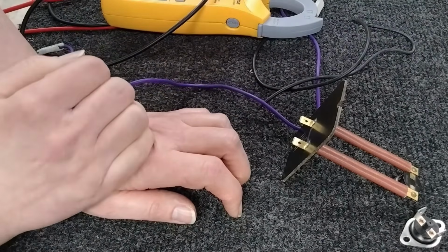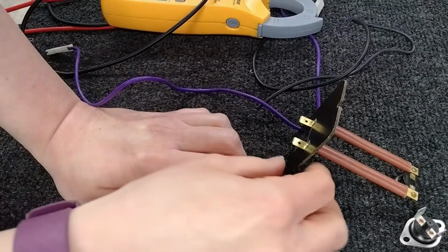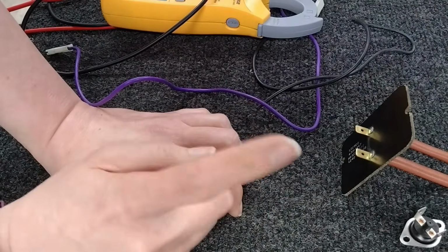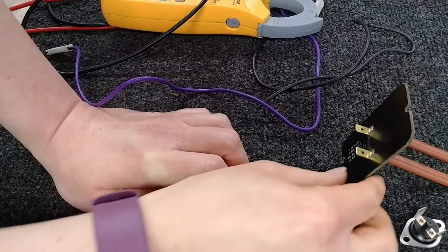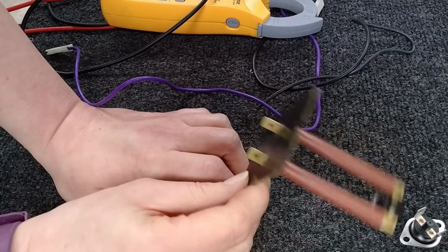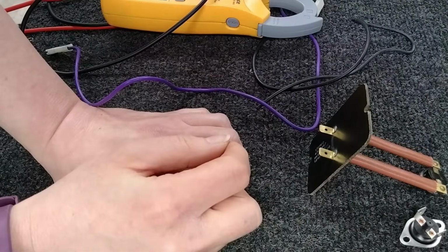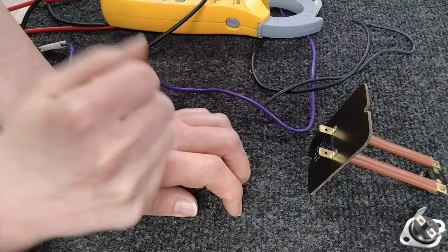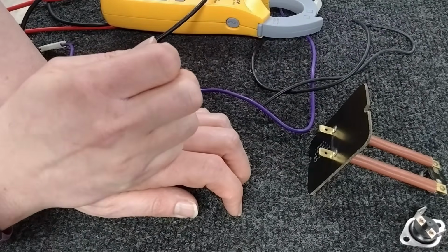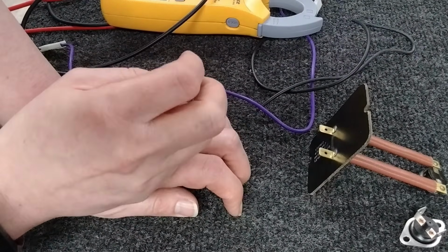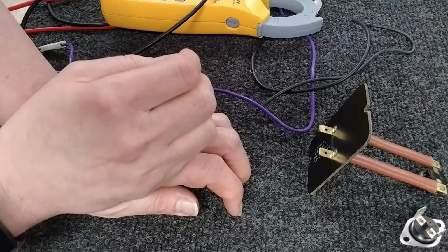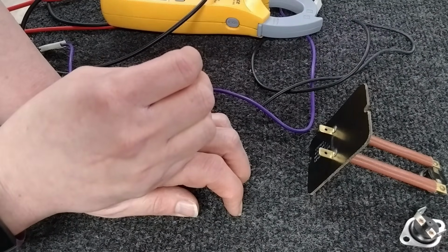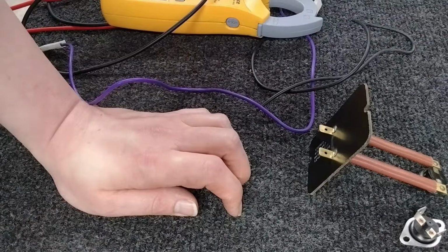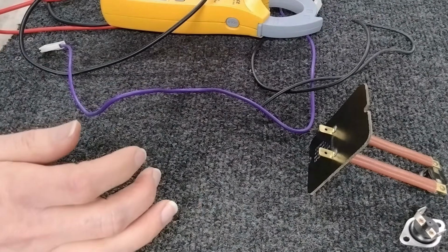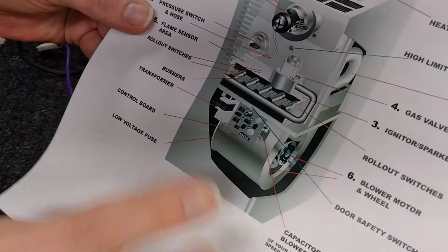If you think you're not up for it, just call a technician, have them come out and clean it up. But I can guarantee your machine is going to function 1,000 times better. So if you're puzzled over something like that, and you're having the same issues, that's probably your problem. Honestly, it's really wise to keep your evaporator coils clean somewhere around every 2 to 3 years, give or take. And a really good way to check that is to check your blower housing, which is going to be that guy down there.